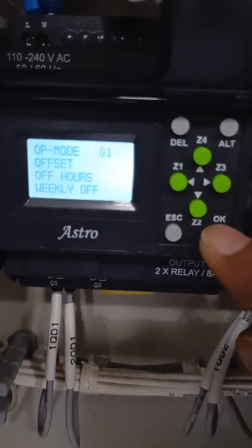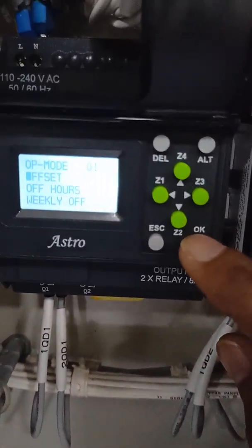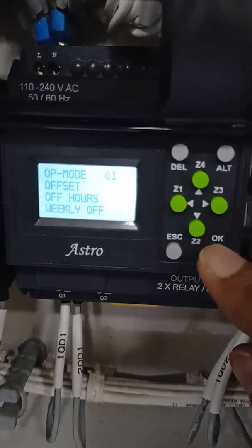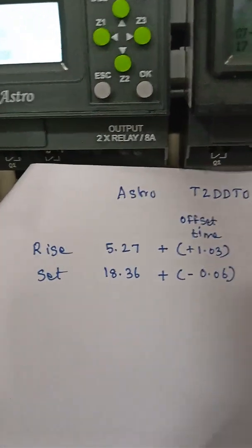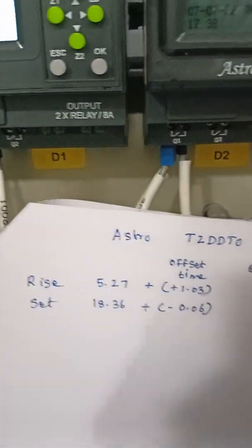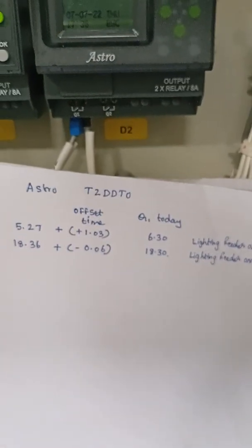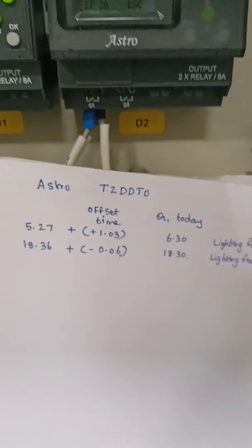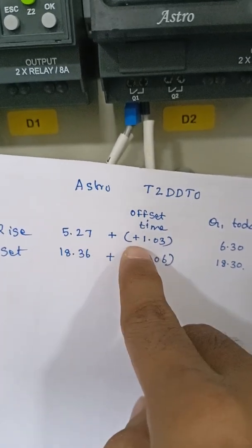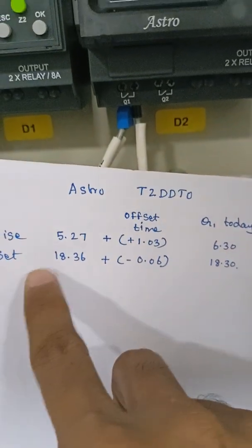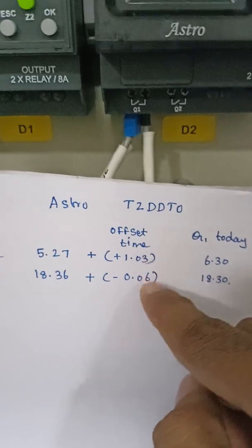The main area is the offset value. By setting the values here, you can turn the feeders on and off according to your required time. I already noted my sunrise and sunset values: 5:27 and 18:36. I want to switch off my feeder at 6:30 in the morning and switch on my feeder at 6:30 in the evening. So: 5:27 plus 1:03 equals 6:30, and 18:36 minus 0:06 equals 18:30, which is evening 6:30. These offset values you need to set in the offset field.